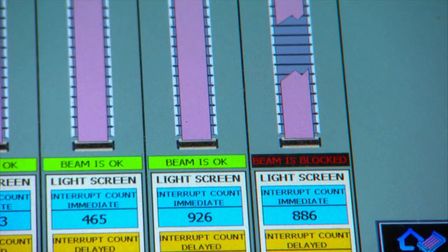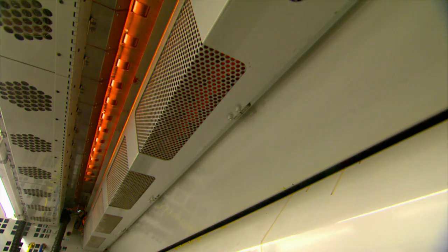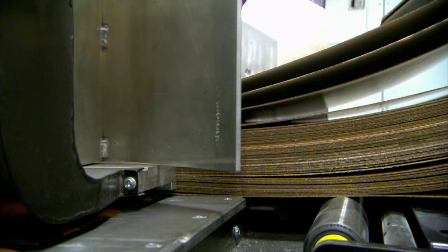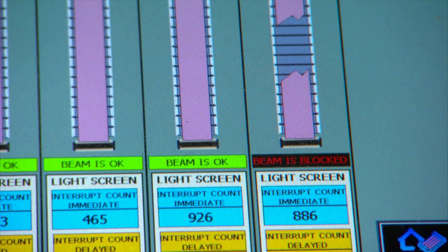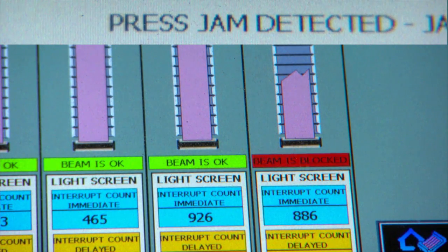If the laser is broken because of a jam or stoppage, the dryers are instantly powered down and board feed is suspended. The fault and dryer position where the intrusion has occurred will be noted on the operator's touch screen. Only when the sheet or debris is removed can the dryer and press be restarted.